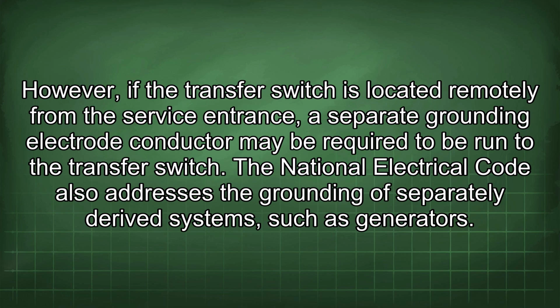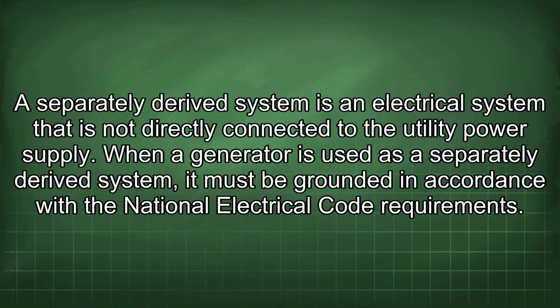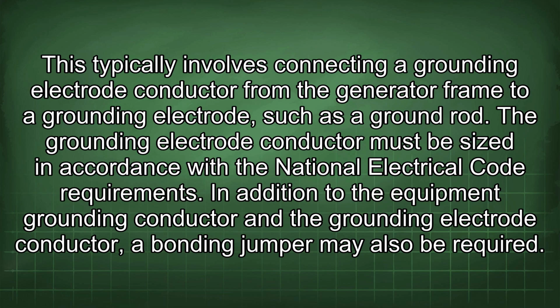The National Electrical Code also addresses the grounding of separately derived systems such as generators. A separately derived system is an electrical system that is not directly connected to the utility power supply. When a generator is used as a separately derived system, it must be grounded in accordance with the National Electrical Code requirements. This typically involves connecting a grounding electrode conductor from the generator frame to a grounding electrode, such as a ground rod. The grounding electrode conductor must be sized in accordance with the National Electrical Code requirements.